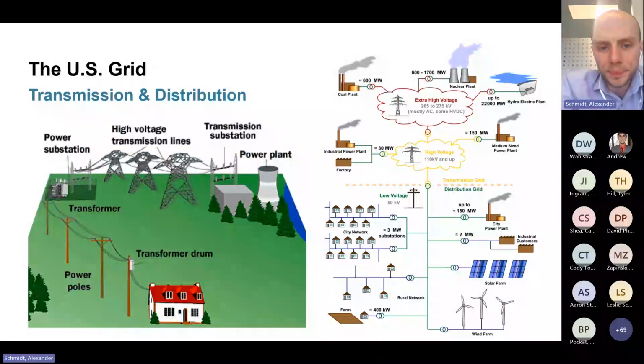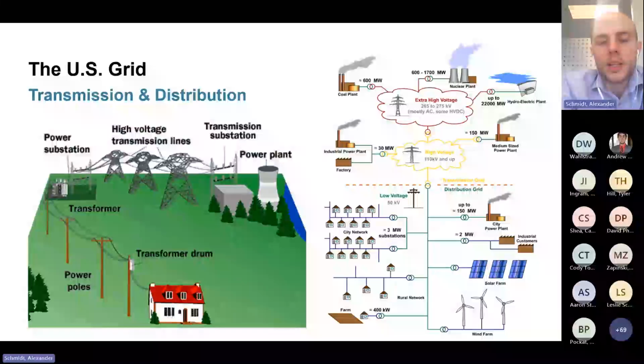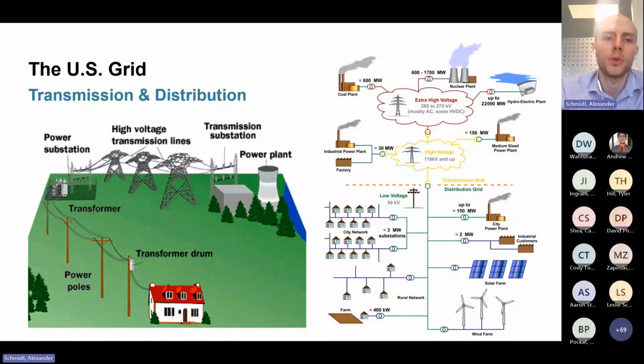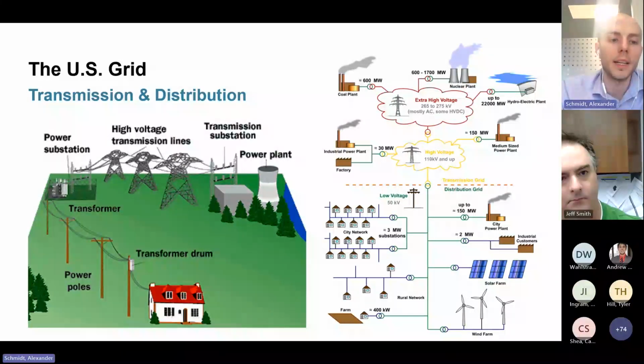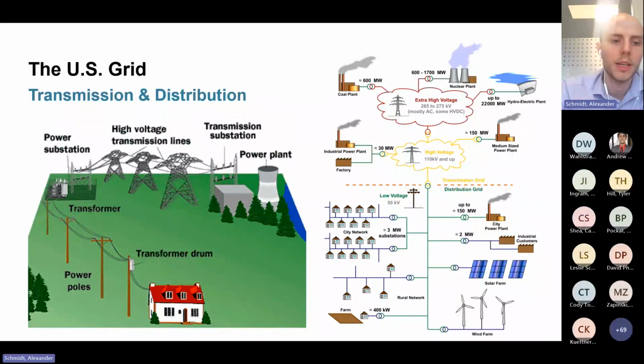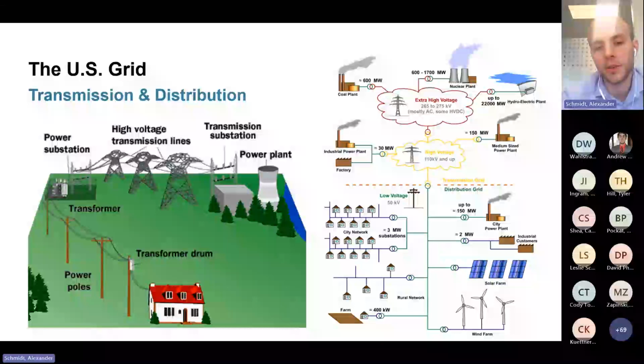You have a power plant, you need some type of generation. That's going to go to a transmission substation where we increase the voltage so we can get it across really long distances. Then we go to another substation where we lower that voltage and put it on distribution lines. Those power poles you see are your distribution lines. Then we go to what you could call another substation - it's just a pole mount transformer - that drops the voltage even further, so it's usable for a house or business, since we don't need to transmit very far once we get to that point.